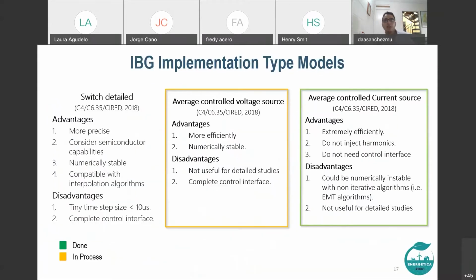So the first task in order to build a generic EMT IBG model was defining the best model type based on our requirements. This slide presents three inverter model types based on their different power electronic interface detail. So we have switch detailed, average controlled voltage source, and average controlled current source. The switch detailed is the most complete and the most precise, but as a disadvantage, it requires a tiny step size, less than 10 microseconds. The average controlled current source, as advantages, is extremely efficient, does not inject harmonics and does not need a control interface. It has a few disadvantages, but in our experience, they are of very little importance.